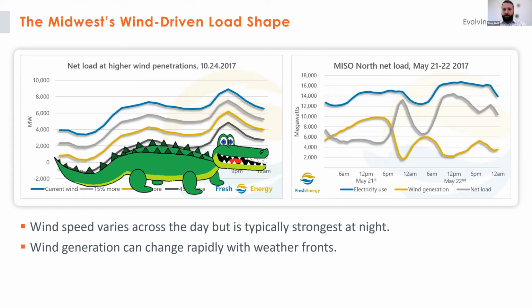Looking at the wind generation for a moment, you can see that at about 6 p.m., a weather front came through and wind generation dropped 8,000 megawatts, bounced back a few hours later up to 4,000, and then dropped again. You can see what the ISO had to do to try to keep track with that, as far as ramping up and down those natural gas plants to maintain their voltage on the grid. That type of event can give the ISO whiplash as they try to balance the load and generation. And oftentimes that results in very high electric prices during a time like this.